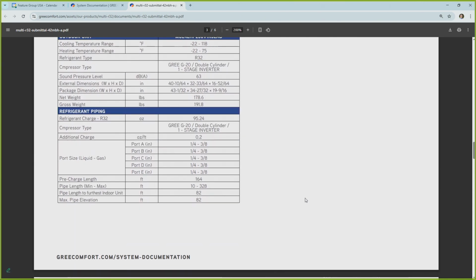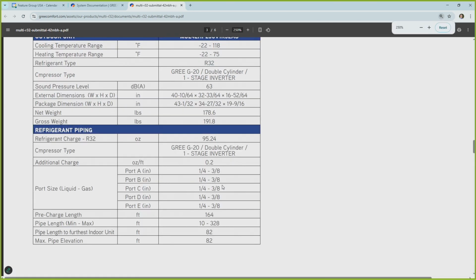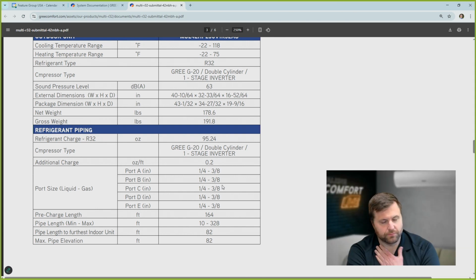You'll see that pipe length minimum maximum that he quoted to you. Minimum is 10 feet to any indoor unit. Maximum total piping is 328 feet. Pre-charge line length is for 164 feet. And there's your pipe length to the furthest indoor unit and max pipe elevation - that's where Justin was getting all that information from. So that's your cheat sheet, guys. That's the best way to do it, go to that submittal and it gives you all your planning, as you'd call it in that question, to be prepared for the jobs ahead of time and know your min-max line lengths and all that kind of stuff.